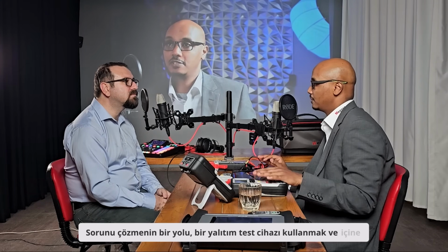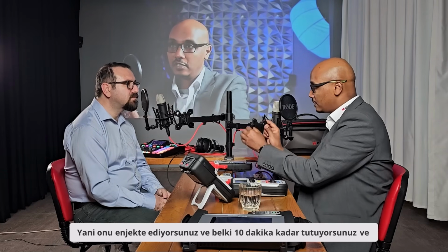So you know there's an issue, here's a practical trick: if you're out to do a survey but it's a bit cloudy, not a sunny day, you won't have enough irradiance for your thermal camera to pick up problems. One way to induce the issue is to use an insulation tester and inject voltage into the system, holding it for maybe 10 minutes, and these problem areas will light up.